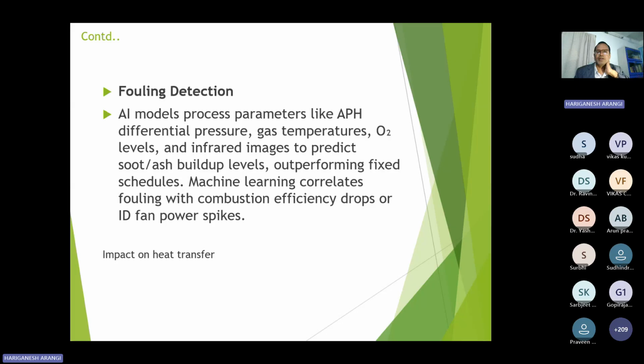Fouling detection also: AI models process parameters like air preheater differential pressure, gas temperature, O2 levels, and infrared images to predict soot buildup levels, outperforming fixed schedules. Machine learning correlates fouling with combustion efficiency drops or ID fan power spikes. This is because if soot blowing is done improperly, or not done at all, ash will accumulate on the boiler heat tubes, the water tubes, and there will be improper heat exchange, and you will not get the proper steam, and boiler efficiency will be down. You need to burn more fuel.